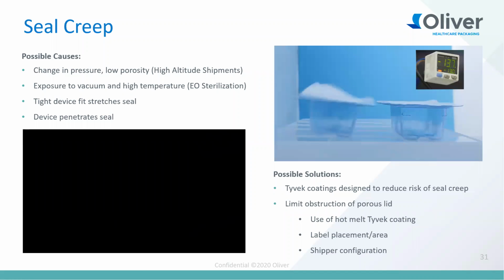The possible solutions are in the bottom right. At Oliver, we have Tyvek coatings designed to reduce the risk of seal creep. We have the coatings and adhesives, like in this tray example on the right, which could have a better resistant coating to changes in temperature and pressure and allow for a stronger seal. But the key here is to limit the obstruction of the porosity. If you have a Tyvek lid, you want to ensure breathability is happening. We have, for example, a hot melt Tyvek coating. Very typical, common coatings are flood coated and cover the whole Tyvek area. Our hot melt coating is more of a dot pattern that allows more porosity. If you're interested, you can reach out to us and we can walk you through the differences.